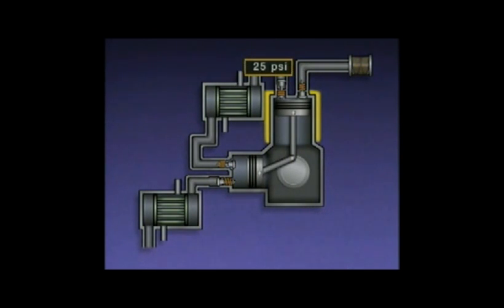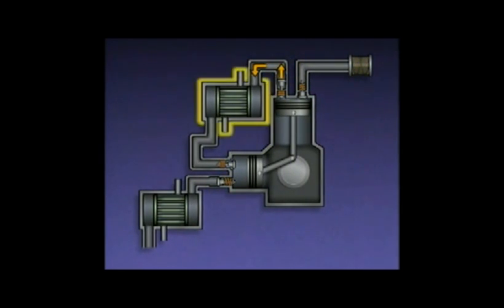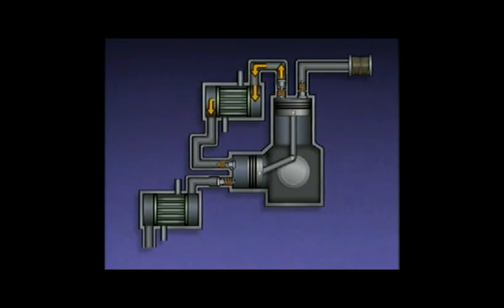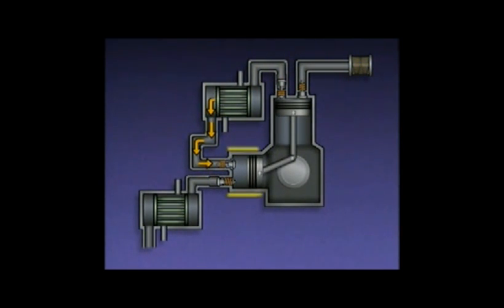As the air is compressed, its temperature increases. The air that leaves the first stage of the compressor is routed to the intercooler, which is a shell and tube heat exchanger. As the air passes through the tubes in the intercooler, it is cooled by water flowing around the tubes. The cooled air from the intercooler is then routed to the second stage of the compressor.